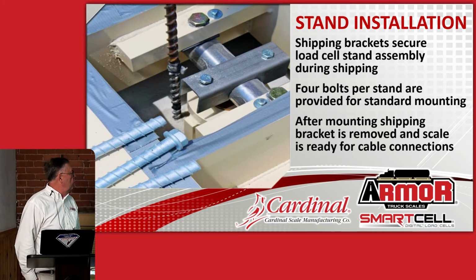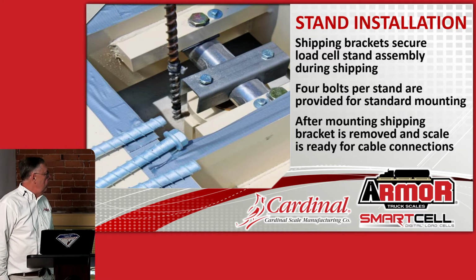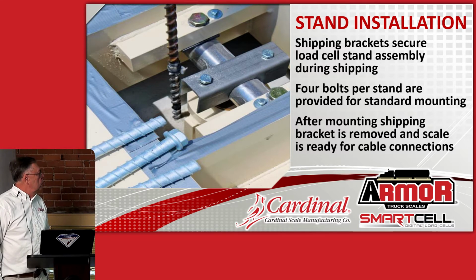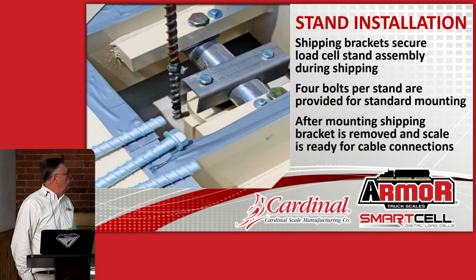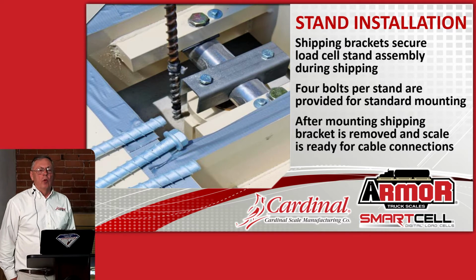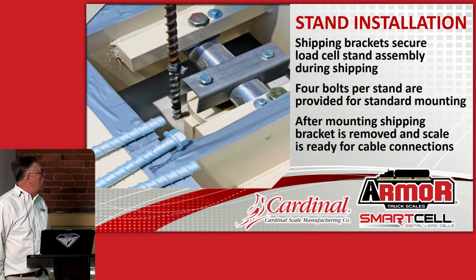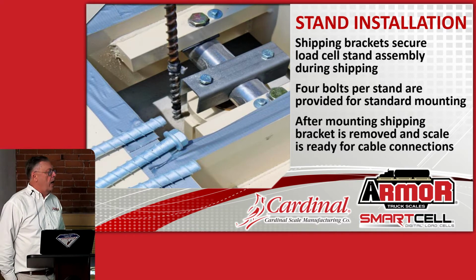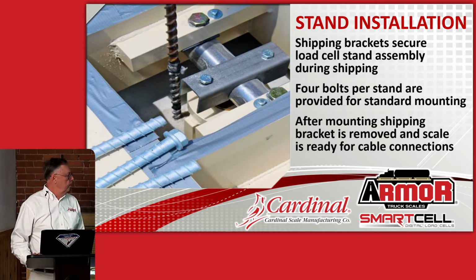But basically, after the stands are drilled and the 4 bolts are tightened, the shipping bracket that's there in the center of the load cell has 2 bolts. You remove those 2 bolts and throw that shipping bracket away, and the scale mechanical installation is pretty much done.